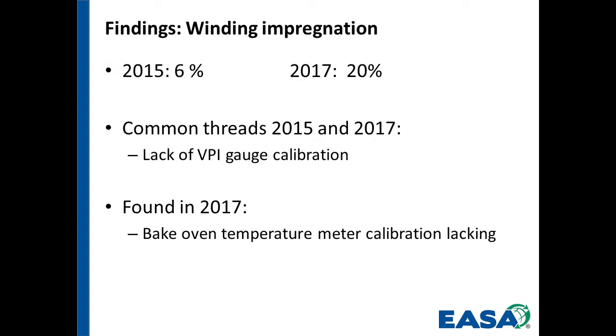Impregnation of the windings, the common thread is a lack of calibration on the VPI. So it's not the standard day-to-day dip and bake that were the big issues. It was the VPI gauges that weren't calibrated. If you're not doing accredited repairs on any of the windings that are VPI processed, you'd label the VPI gauges for reference only. But again, if you do that, then you can't accredit a repair that's been VPI processed.